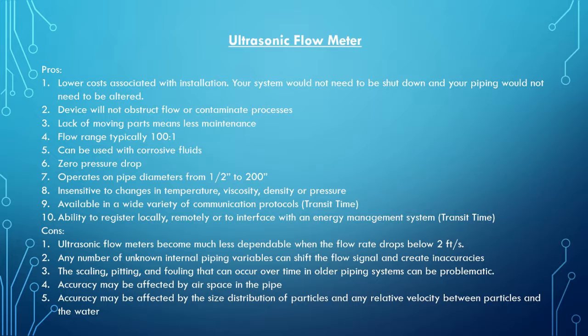On to the cons. Ultrasonic flow meters become less dependable when the flow rate drops below 2 feet per second. Any number of unknown internal piping variables can shift the flow signal and create inaccuracies. The scaling, pitting, and fouling that occur over time in older piping systems can become problematic. Accuracy may be affected by airspace in the pipe. And lastly, accuracy may be affected by the size, distribution of particles, and any relative velocity between particles and water.